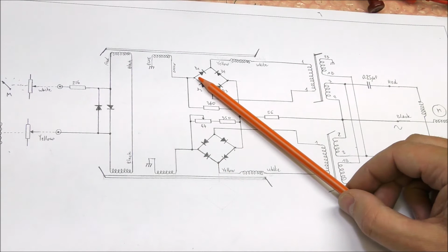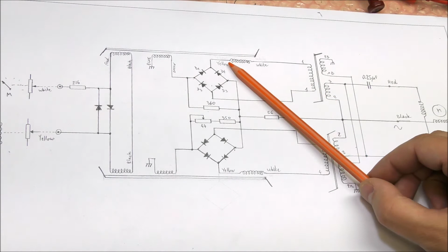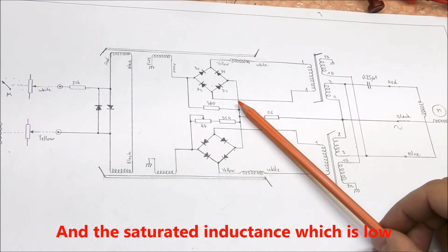Okay, so there will be an increase of the DC current which will flow into these two windings here. So this DC current will try to saturate this transformer and this one also, because the windings here are connected in series. So when this transformer saturates, this will decrease the impedance of this winding here. This point will be connected more or less to the ground. There will be only the DCR of this winding.